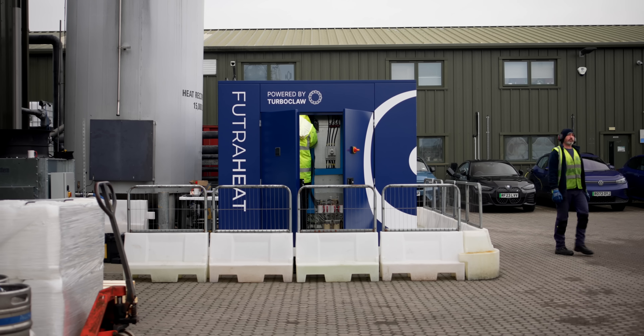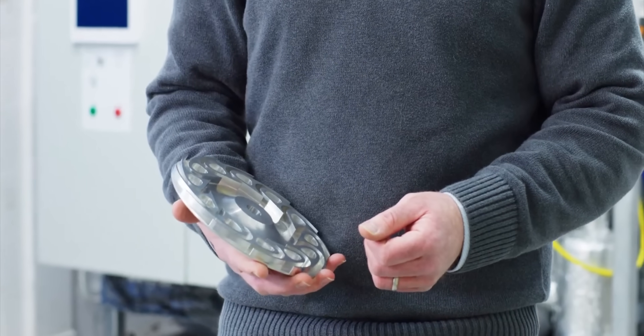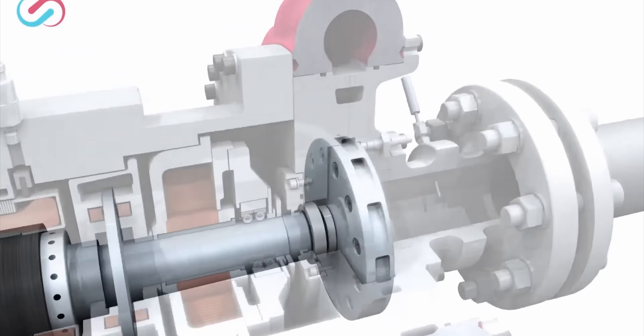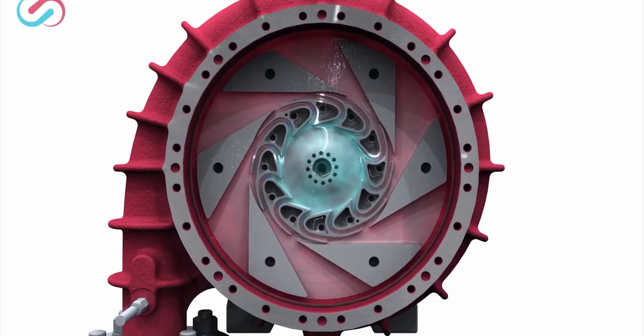The world of turbo machinery has existed for so many years — we really understand steam turbines, for example — and yet we haven't seen them in this application before. It comes down to the fact that TurboClaw is able to operate as a turbo compressor in this sub-megawatt high temperature heat space. Probably a third of all applications for this kind of heat pump are in this lower sub-megawatt space, so that's where the pull is, and until now there hasn't been a turbo compressor solution. TurboClaw's geometry is entirely different from a normal turbo compressor — it's not a gradual evolution, it's a complete step change, something totally different.